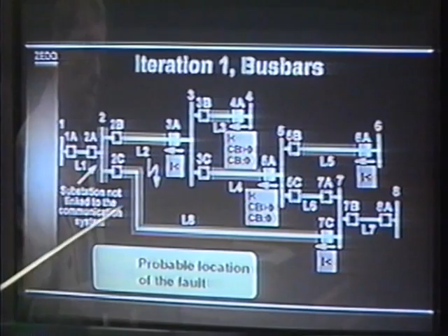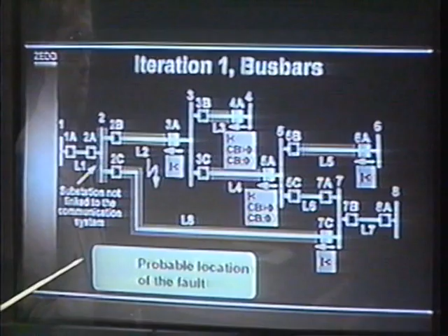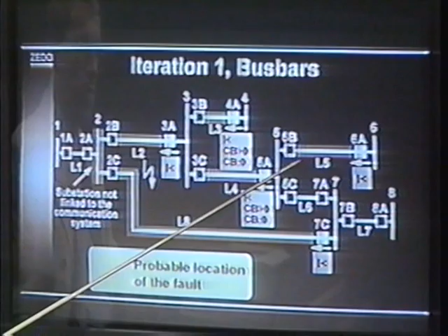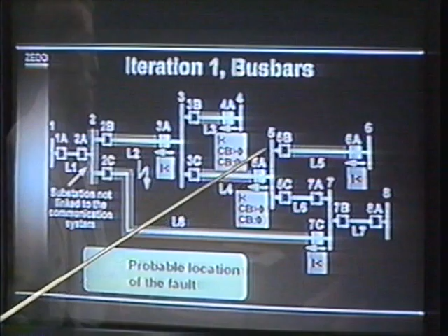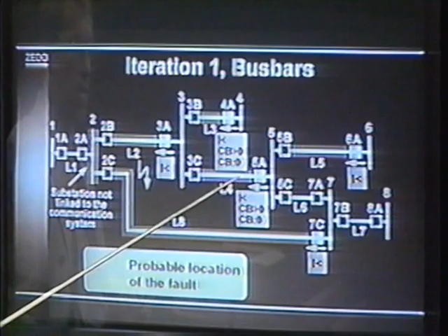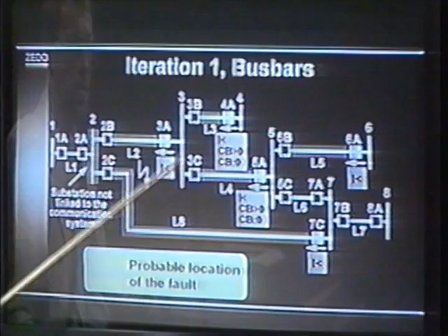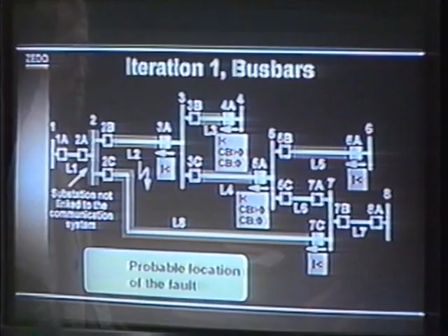We can see that busbars 5 and 3 are not called a probable location of the fault. On the one hand, the intermediate diagnosis generated for line L5 indicates that the fault may be on the line or further on the left side, which would give evidence that the busbar has to be called a probable location of the fault. But on the other hand, the intermediate diagnosis for line L4 says that the fault can be on the line or left of it. This is contradictory to busbar 5 being a probable location of the fault. The same arguments are against busbar 3 being part of the probable location of the fault.